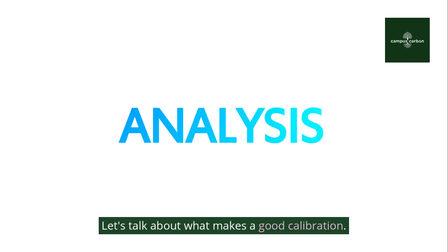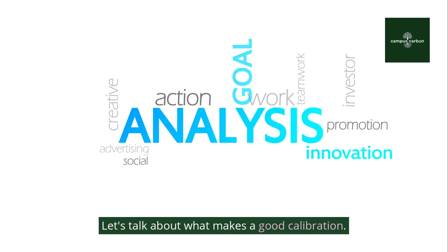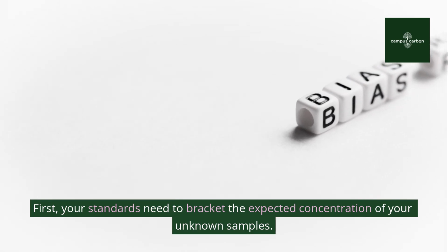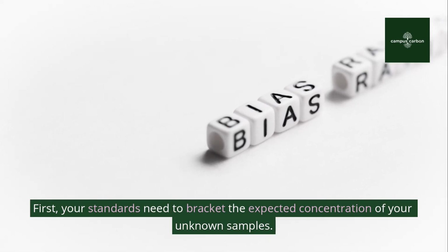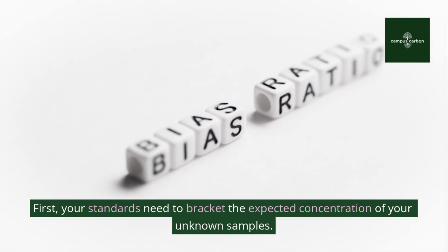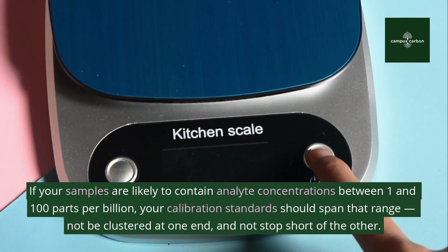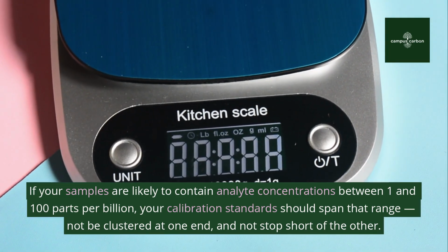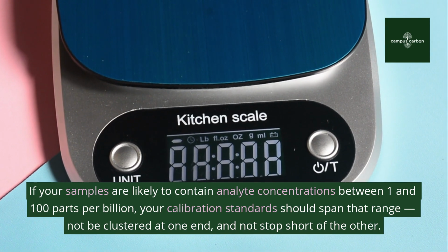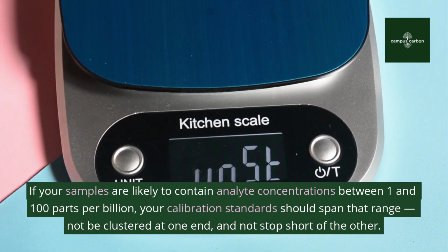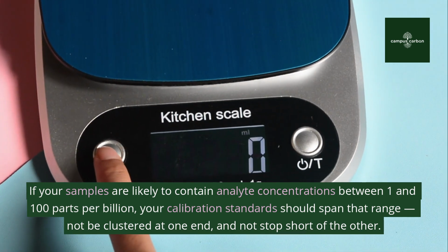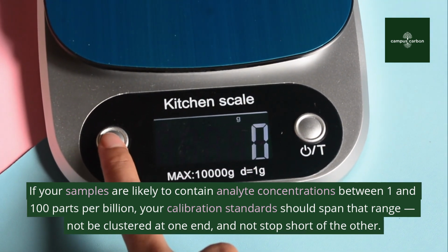Let's talk about what makes a good calibration. First, your standards need to bracket the expected concentration of your unknown samples. If your samples are likely to contain analyte concentrations between 1 and 100 parts per billion, your calibration standards should span that range, not be clustered at one end, and not stop short of the other.